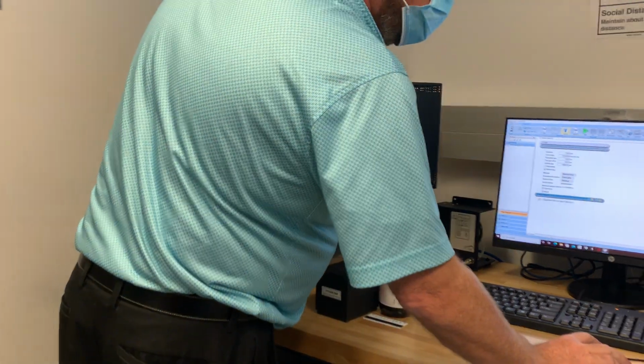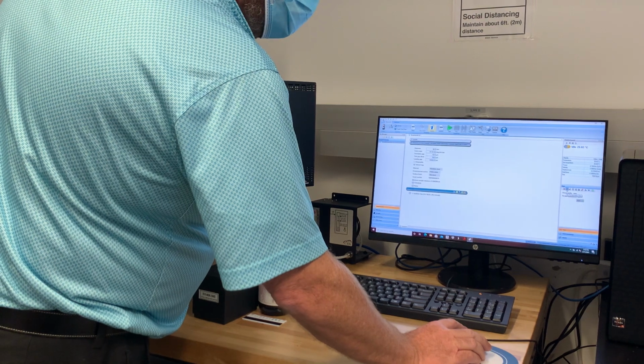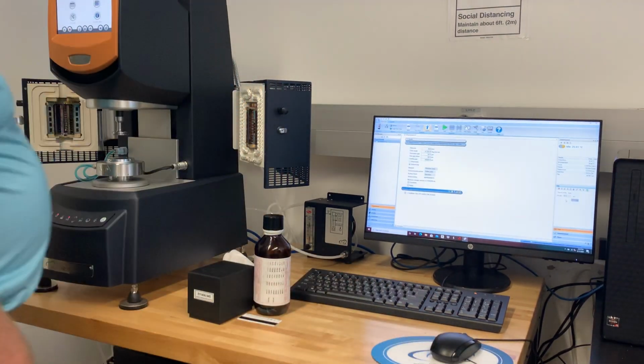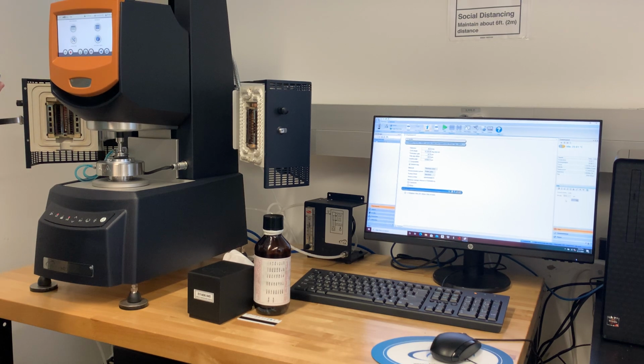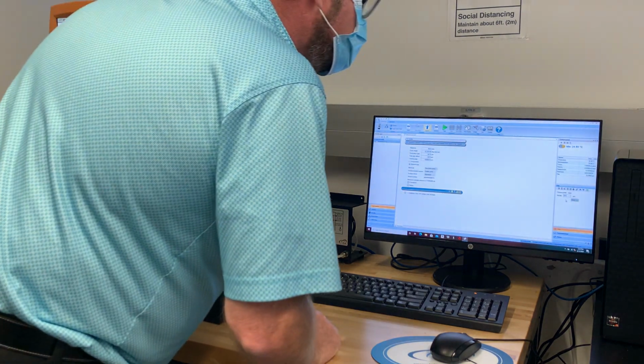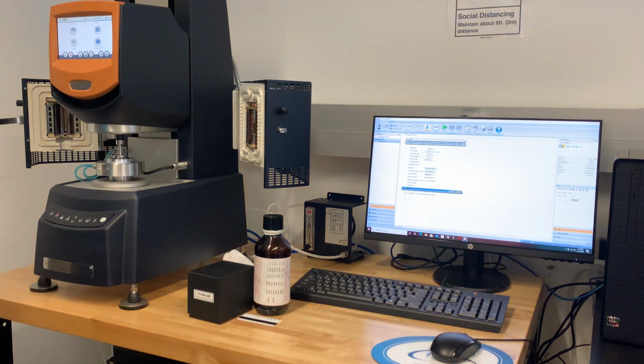Okay, so now I can go to geometry gap, and it should go to 52 microns. Okay, so we're at 52. I have extra sample on here. What do I need to do? Wipe it off. I need to trim it, because if you have too much sample around the edge of the geometry, your viscosity will be high.